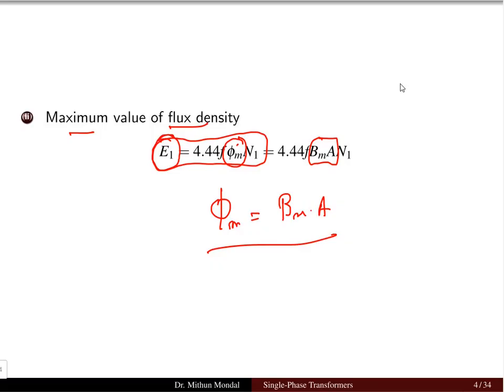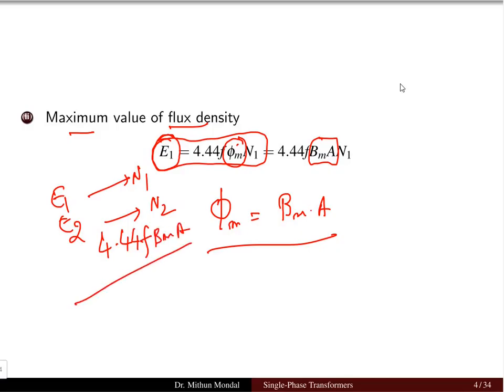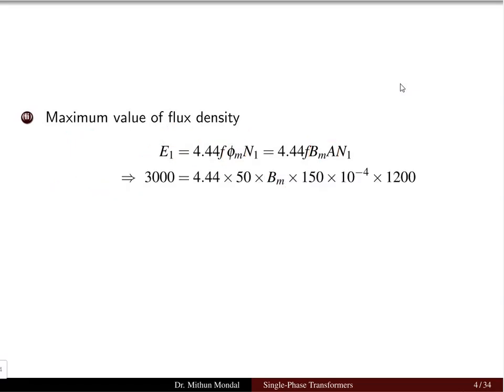When we are taking the secondary EMF, then the number of turns we have to take is N2. If we are taking E1, then the number of turns we have to take is N1. The rest of the formula remains the same, that is 4.44 times frequency times Bm times area, and then we multiply with either N1 or N2 to get E1 or E2. Once we substitute the value of E1 and the other data, the only unknown is Bm, which we need to find. So Bm we can easily find as 0.75 Weber per meter square. This is the maximum value of the flux density.